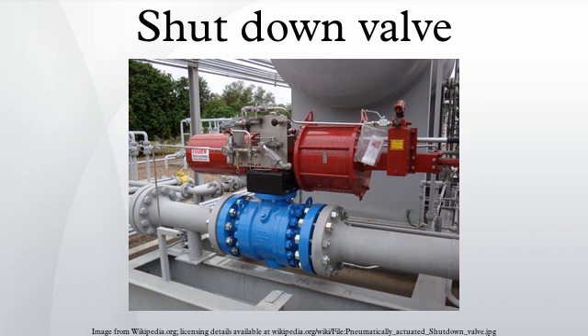In addition to the fluid type, actuators also vary in the manner in which the energy is stored to operate the valve on demand. A single-acting cylinder, or spring return, stores energy by means of a compressed spring. A double-acting cylinder stores energy using a volume of compressed fluid. The type of actuation required depends upon the application, site facilities, and the physical space available, although the majority of actuators used for shutdown valves are of the spring return type due to the fail-safe nature of spring return systems.